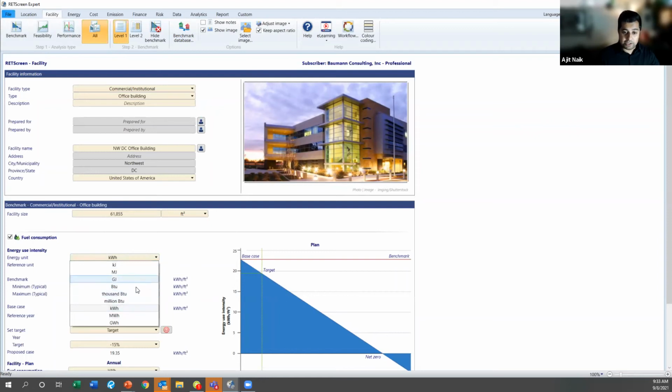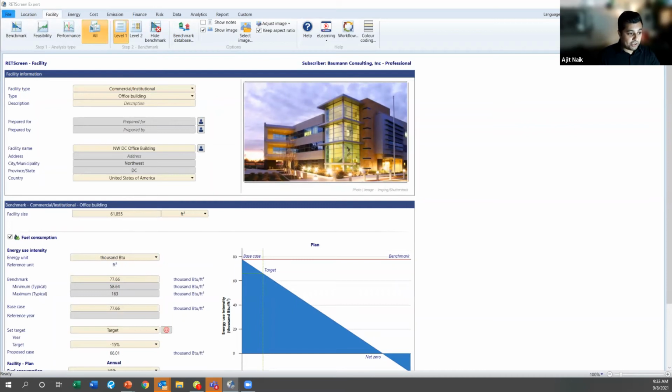This is the US, so we use BTUs to represent EUIs. And we determined via Energy Star Portfolio Manager, as discussed earlier, that an Energy Star score of 71 correlates to a site EUI of 49.7. The building, based on real world actual measured data from utility bills, had an Energy Star score of 66, which correlated to an EUI of 53.3.